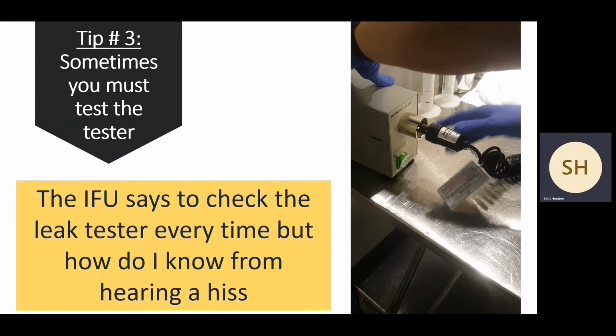Tip number three, sometimes you must test your tester. Now, I know this turns into a bit of a rabbit hole. Sometimes you say, well, I use a leak tester to test if my scope is working, and now you're telling me I should test the tester. Well, that's absolutely true. This is a very important step in whether this process works, right? And because the one that's pictured is an Olympus unit, that has a motor and gaskets and seals and all these things that could fail, well, if that device were to fail, then your leak test itself would fail. So we've got to roll that a step back and then say, yes, we do need to check this.